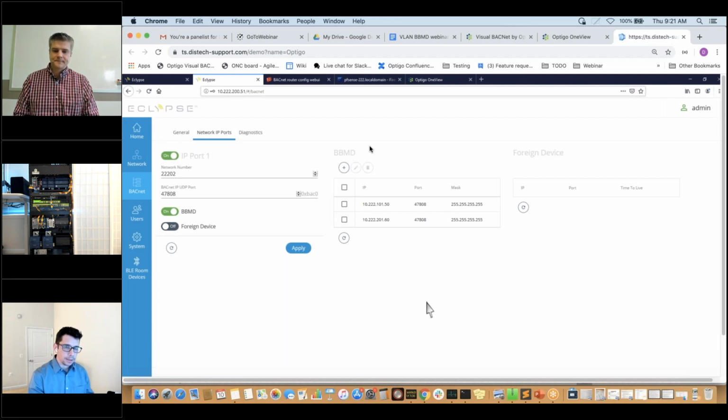If you're just troubleshooting an MSTP bus, if possible. And the less you have that BBMD, the device doing the less things it's doing, the better. It has a big job already if it's trying to route all of that broadcast traffic across these networks. So if you can, and if your architecture supports it, it's better to have a BBMD just do that job. I know that's not typical with older systems because you have a router and that's always your BBMD. But now with all these IP devices around, being able to serve dual functions, if I have a few Eclipse controllers, I will always make one Eclipse controller a BBMD and then let the other one do routing, but I'll try not to mix it on that subnet. I'll try to give them separate jobs.